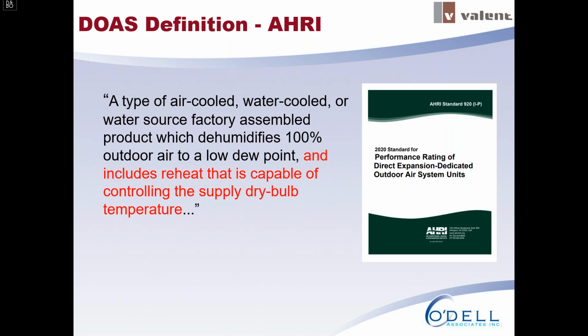You're treating a ventilation air, usually 100% outside air, can be a little bit less than that. The advantage of a DOAS is that instead of dehumidifying and reheating all of the supply airflow, which for a standard rooftop would include a mixture of outside air and recirc air, you're really only dehumidifying the outside air. So this allows you to have better dew point control, and it's much more energy efficient. In addition to that, you're bringing in outside air. Typically, you want to be able to measure that and prove that you're meeting ASHRAE 62.1 ventilation rates. And having a DOAS unit allows you to do that much more easily than if you're bringing in outside air at multiple different locations.